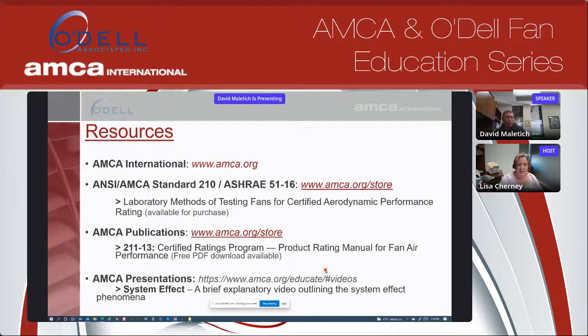These are resources that Dave referenced during his presentation. ANSI AMCA Standard 210, which is also done in conjunction with ASHRAE 51-16, is available for purchase on the AMCA store site. AMCA Pub 211-13 is currently available. It's a free PDF download. So if you go either to this web address or just go to the AMCA website and look up publications and standards, you can access that download. And we also have an online system effect video. It is not the same video you just watched. It's about a 2.5 to 3 minute video that outlines the basic concepts of system effect.